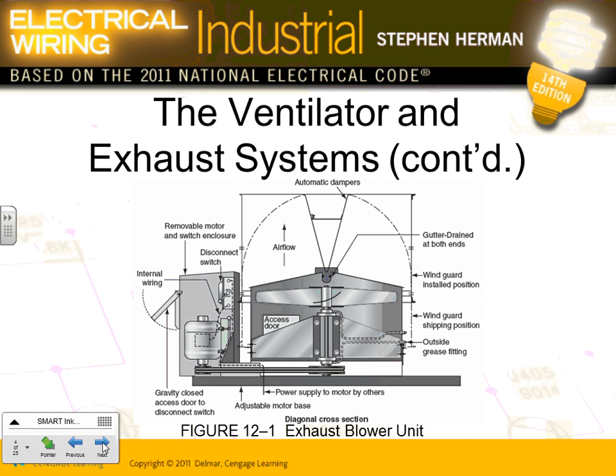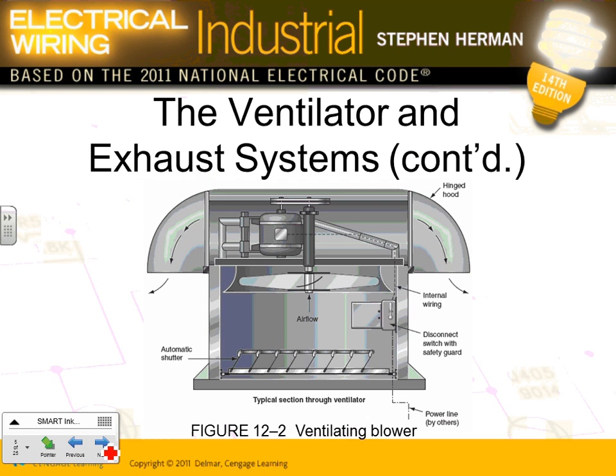What's on the roof? How many of these do we have? You guys have a new project, five of them on the roof. You're going to install these five on the roof. It looks similar to this. And my job and your job, guys, is to bring, here's a disconnect. Can you see the disconnect? We're going to bring a branch circuit to feed this exhaust fan. What does it do for a living? It exhausts air from the building as part of your heating, cooling, and ventilation system, or building automation system. Any comments, any questions, guys, about this? So that's your exhaust fan with your exhaust fan blower.